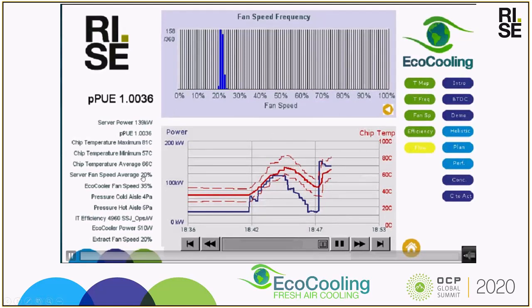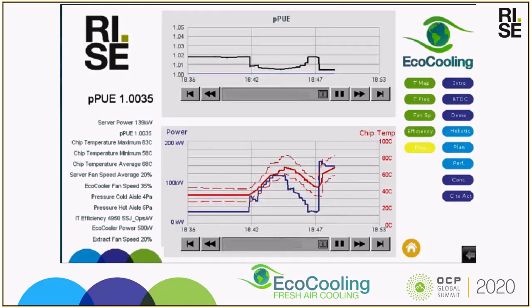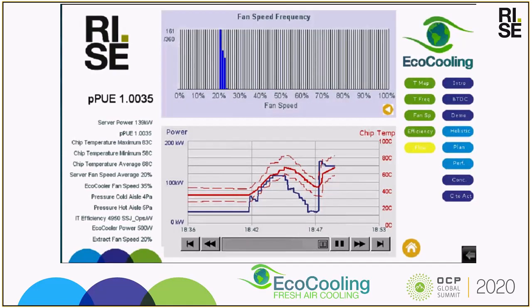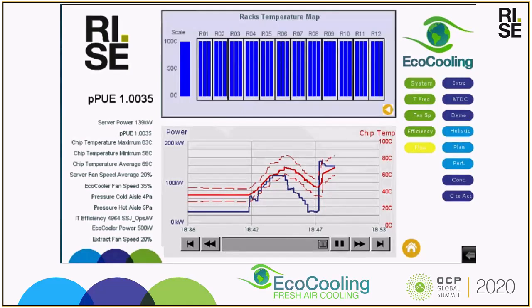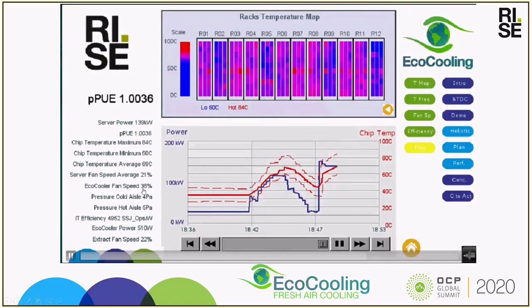At some point, the average of the server fan speeds will increase and then the eco-cooling fan speed will respond to that immediately because of the communication that we've developed over Modbus between what the servers need in terms of their airflow and what the supply fans can give in the eco-coolers. Right, we've just gone to 21% now, and so the eco-cooling fans have gone to 38%. The extract fans are synchronized to the supply fans, and so they have jumped a little bit.